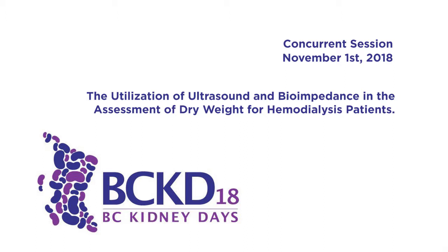And so there's lots of machines available, and I'm not sponsored by any of these companies, but just anecdotally, the most common one that's available is the Fresenius BCM or body composition monitor machine, and it uses multiple frequencies. So basically what it does is send an impulse with low frequency and high frequency. The high frequency can go throughout the body and measures total body water. The low frequency can't get into the cells, so it's only measuring the extracellular water.